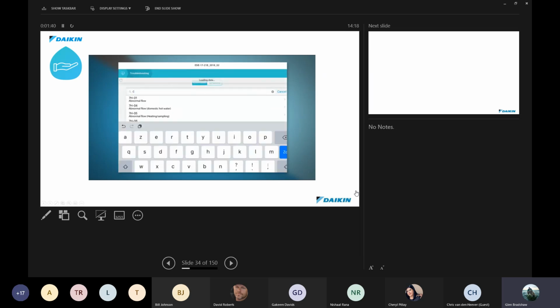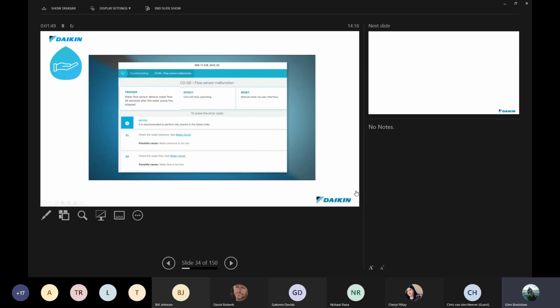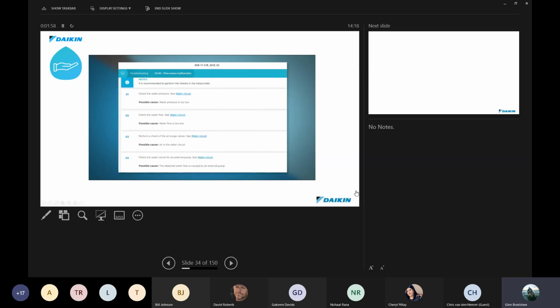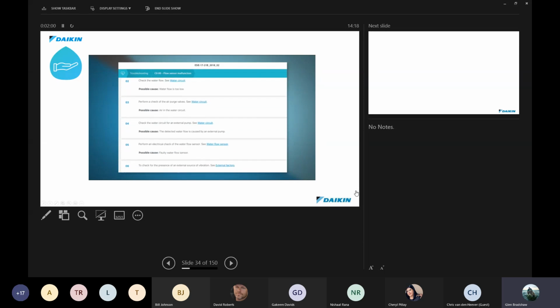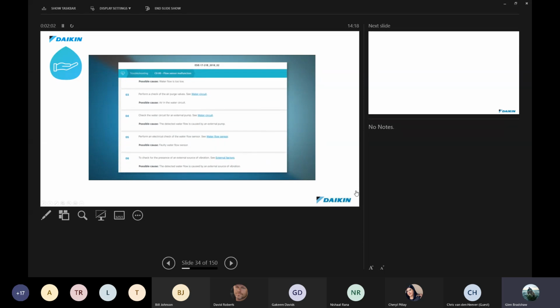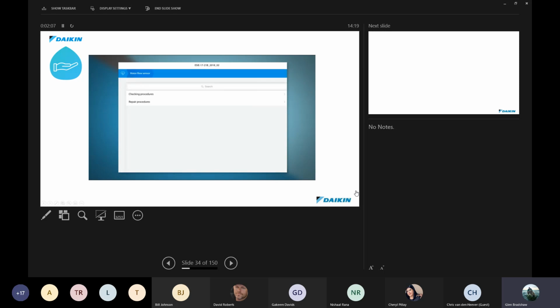A full list of all error codes is provided. You can find your applicable error code by scrolling or by entering it into the search bar. We give you the trigger for each error code, the effect this will have on the unit, and how to reset the error code after you found the root cause. EDoctor guides you in how to solve the error code by giving you a list of components to check in a recommended order. Let's check, for example, the water flow sensor. By pushing on this tab, EDoctor continues the component check of the water flow sensor. We want to check the component.